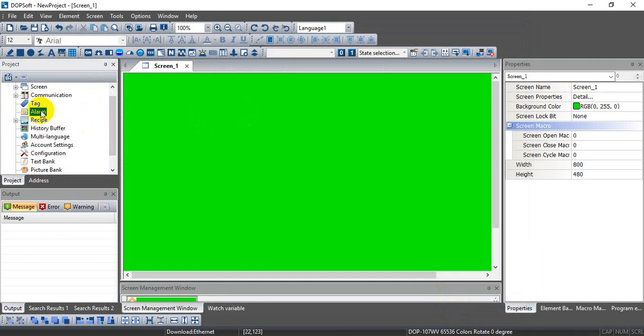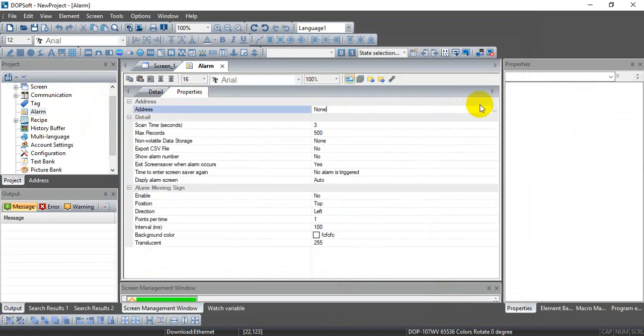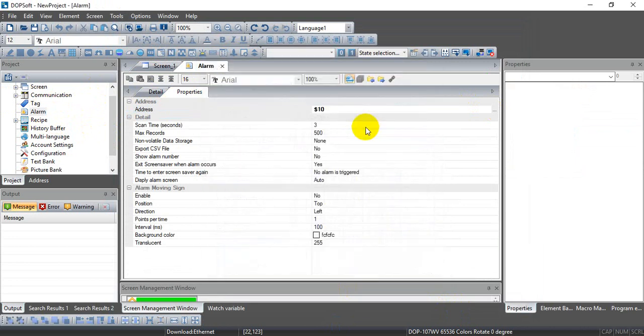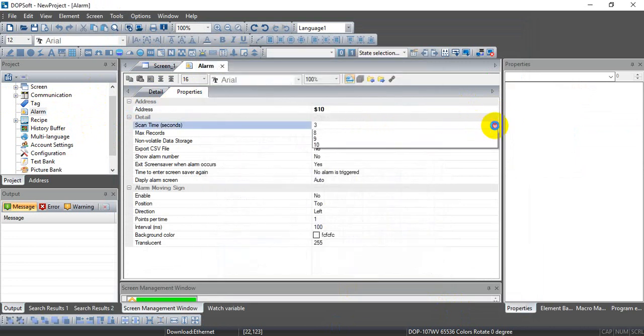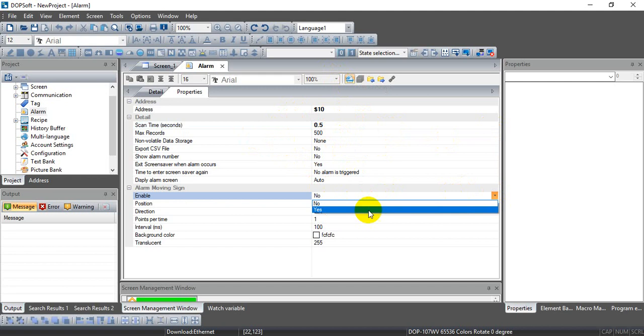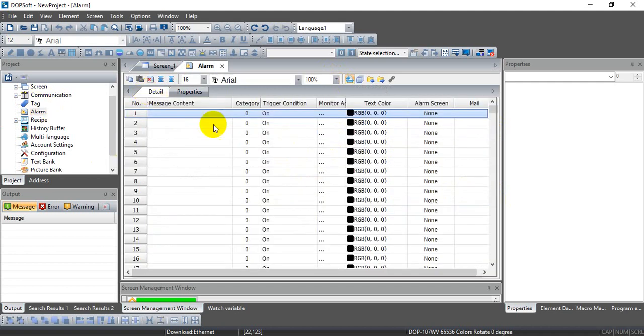Next we go to the Alarm section. Here we define our HMI internal memory address and set the trigger condition. For the scan time we can select a shorter interval — instead of three seconds we use a shorter scan time for this example. You can then give the message content for the alarm.